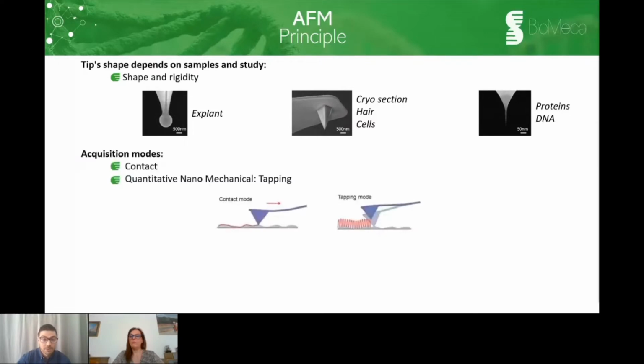Then to perform the experiments, we have different kinds of acquisition modes. The first one is the contact mode. With this mode, the tip is all the time in contact with the sample. And the force applied remains constant because of a piezomotor, which controls the tip's height and adapts its position. And with this mode, we obtain only the topographical data of the sample.